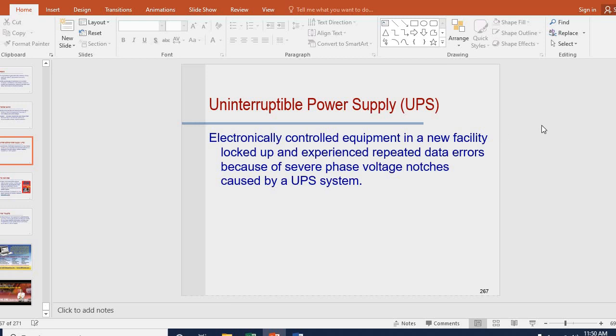See a lot of UPSs, uninterruptible power supplies. We used to use them so that if you lose your AC on something like a computer or PLC, the UPS would hold it up, we could communicate, and we would have a set of contacts on the AC side so we'd know it was down or up, but we could keep communicating with the SCADA system by UPS. It would hold it up long enough. Usually the electrical guys would get it serviced, get power back on. So a lot of power supplies are used in the water, wastewater industry.